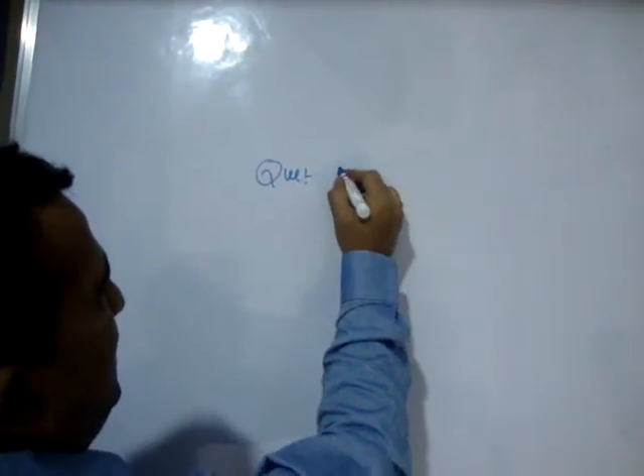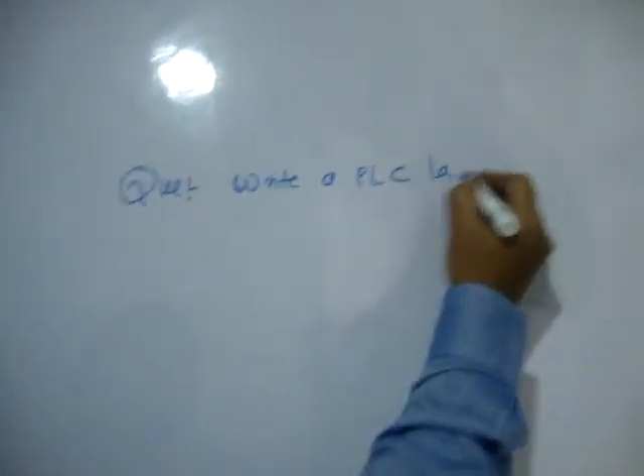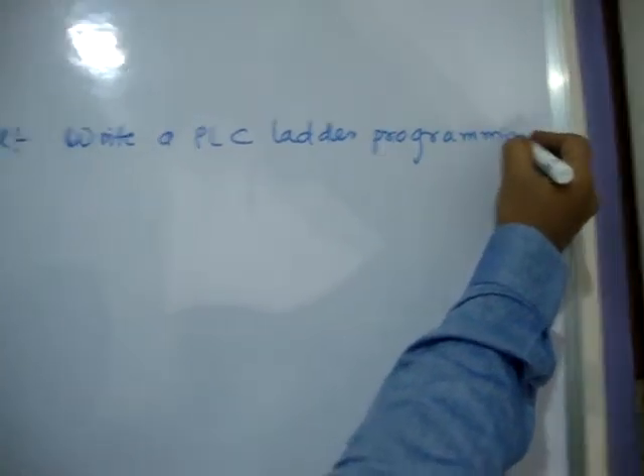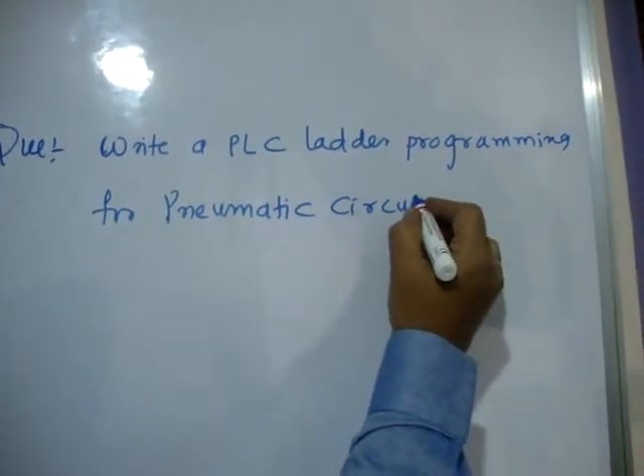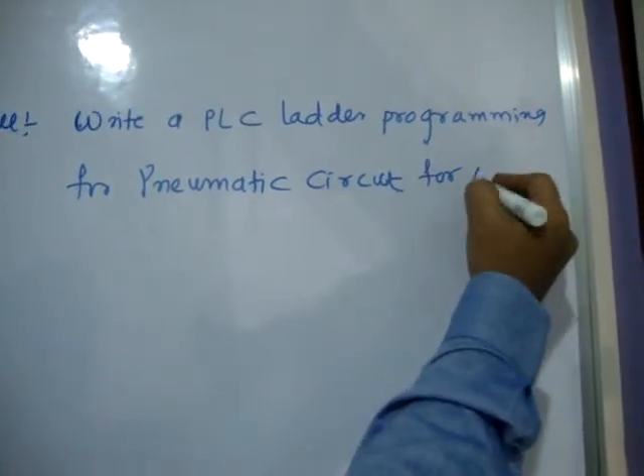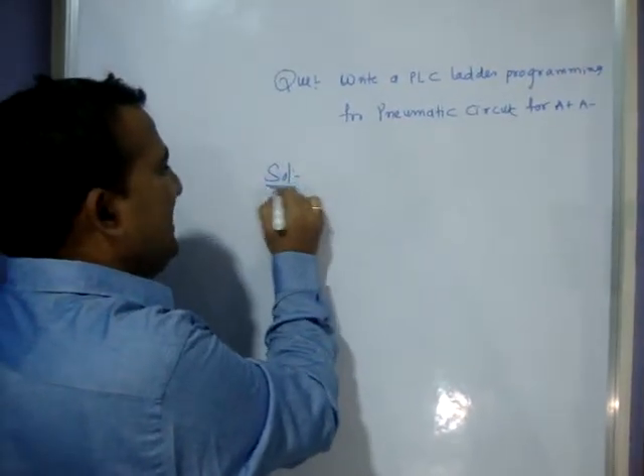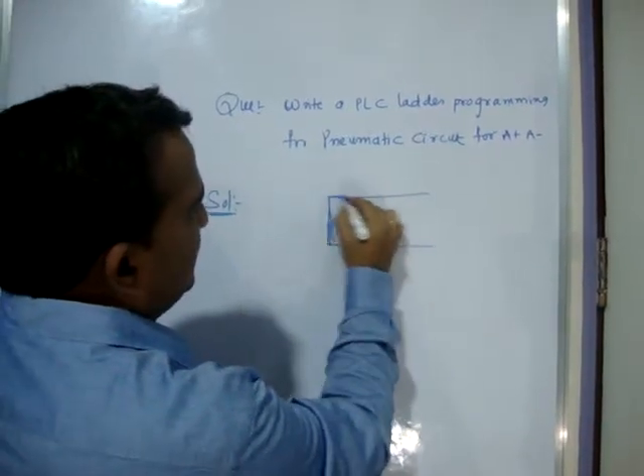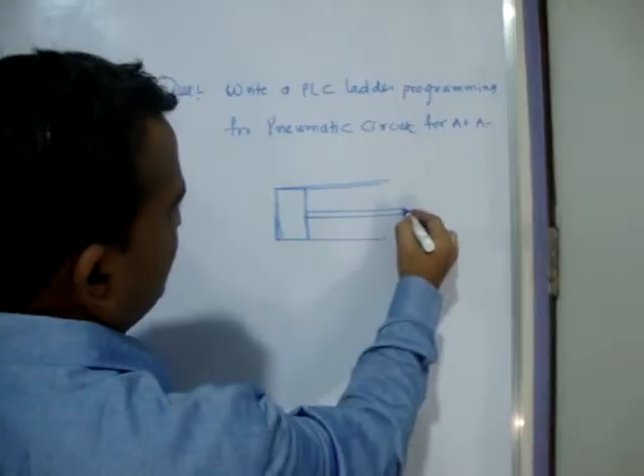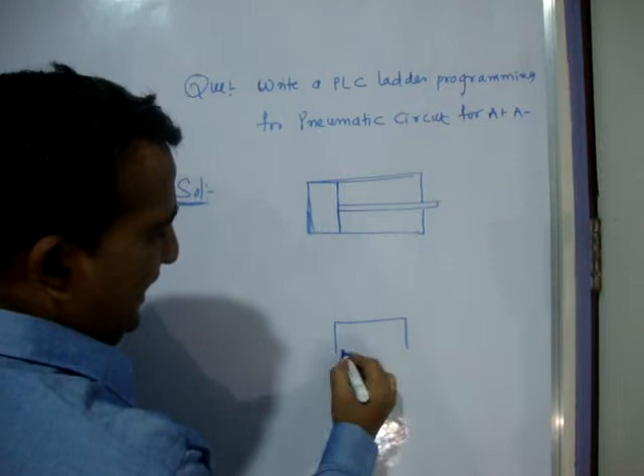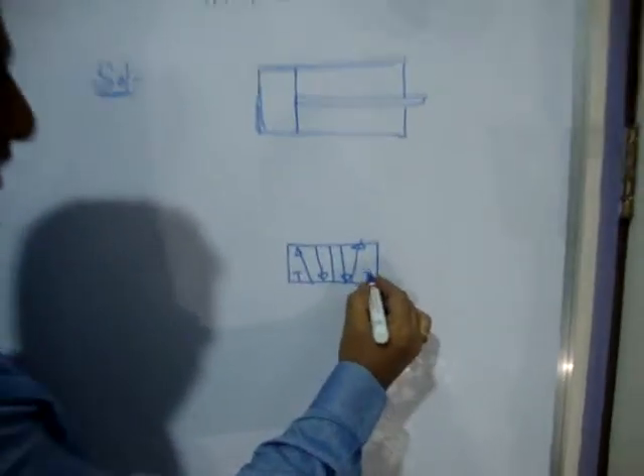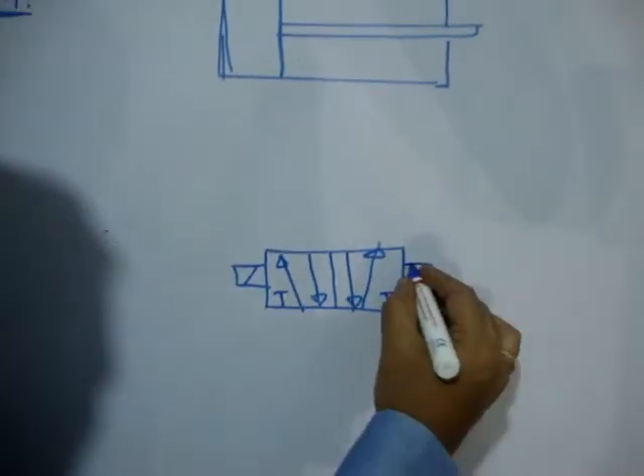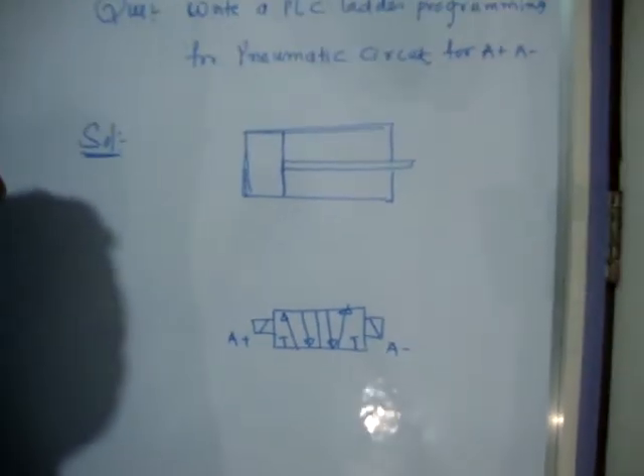In a pneumatic system, the question is: write a PLC ladder program for a pneumatic circuit, especially for A-plus and A-minus. First there are two parts. In the pneumatic circuit, I will take a double acting cylinder. I will take a 5/2 solenoid valve — both sides have a solenoid. This side is called A-plus and this side is called A-minus.